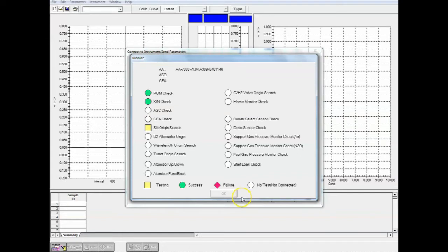So now we have a pop-up that's doing a series of initialization checks. Okay, so it goes through a series of checks. You'll notice that there are a couple here that are giving us white circles, which means no test, not connected. And that's because this one is the auto sampler that I already mentioned we don't have, so there is no auto sampler to check. The other one, GFA, that's the graphite furnace. Okay, we also don't have a graphite furnace. This AA is just flame. Okay, so those are fine. We'll let it go through the rest of the checks.